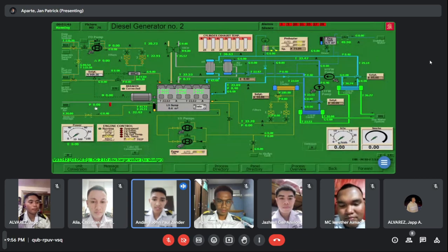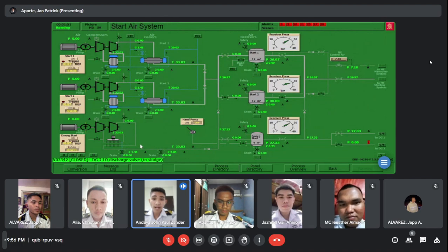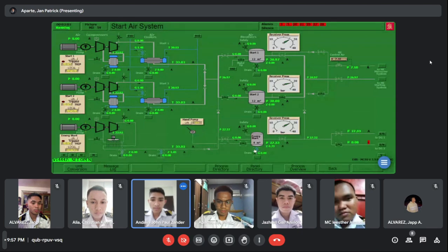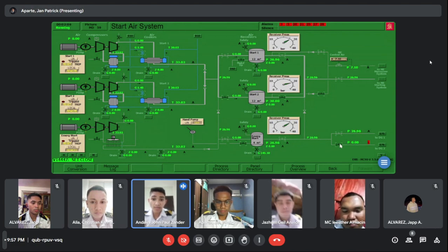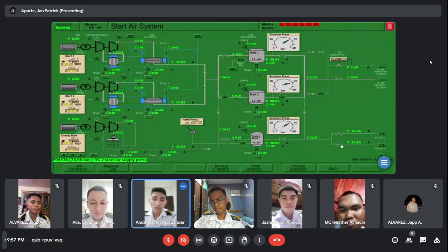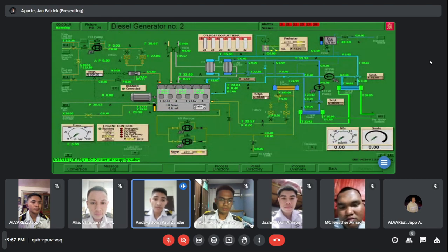Then let's go to the start air system. Before opening the valve in the start air system, make sure to drain the tank of the start air system to remove the contaminants. After draining, turn on the supply air valve of the air system going to DG number 2. After it is on, let's go to the seawater system.